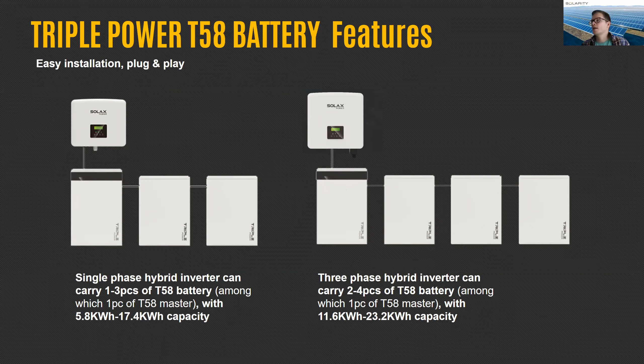Sometimes there are questions whether we can actually connect more than 4 batteries together. The answer is yes. You can connect a maximum of 8 batteries, which will give you a total capacity of 46.4 kilowatt hours for the 3-phase solution. For the single phase solution, you can connect 6 batteries. You need to make sure to connect the same number of batteries to each side. As you see here, it's connected 3 and 3. So you cannot connect, for example, 2 and 3, or 2 and 4. It should be equal numbers, like 3 and 3 or 4 and 4.